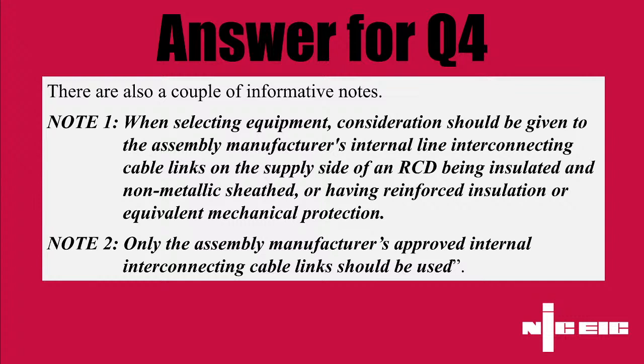Yeah, I think for me, just breaking into two, the two that come to the top of my head. One, totally right, maintaining the integrity of the supply, 100%. And if you can design it in, you mitigate any sort of nuisance tripping, whether that's taking that circuit out, etc., so having your dedicated supply is a good idea. But also, again, referring to manufacturer's instructions, as you always do, Sam, is always a good shout. If there's a specific requirement within that, then you go that route. But even without the manufacturer's instructions, I would like to ensure that supply is maintained and that there's minimal risk of it being disrupted, shall we say, in normal use.